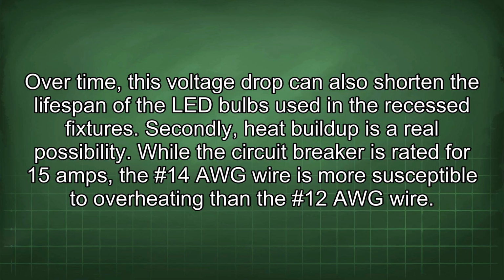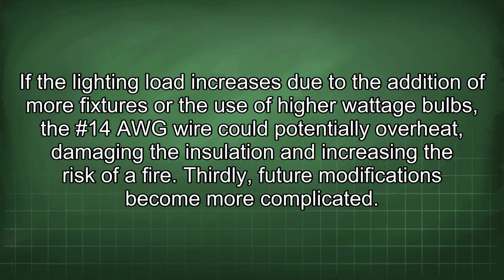Secondly, heat buildup is a real possibility. While the circuit breaker is rated for 15 amps, the #14 AWG wire is more susceptible to overheating than the #12 AWG wire. If the lighting load increases due to the addition of more fixtures or the use of higher wattage bulbs, the #14 AWG wire could potentially overheat, damaging the insulation and increasing the risk of a fire.